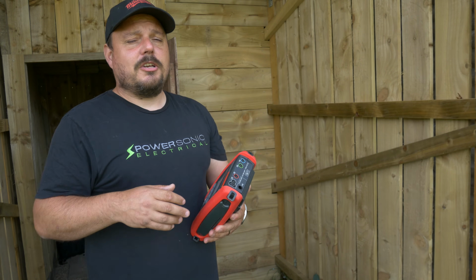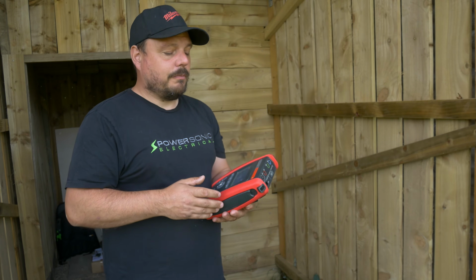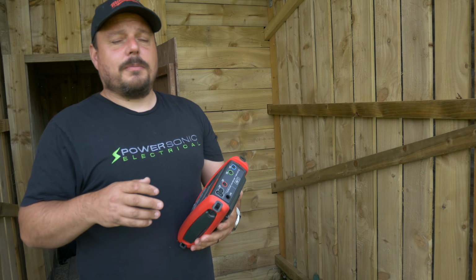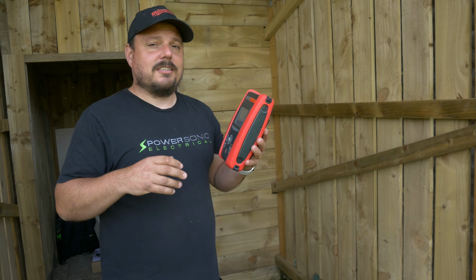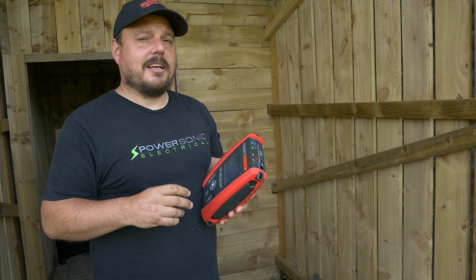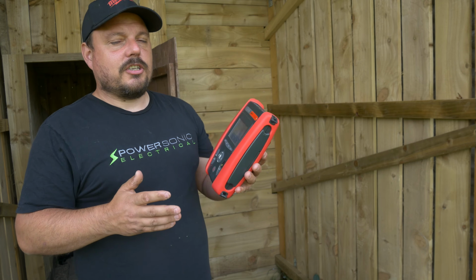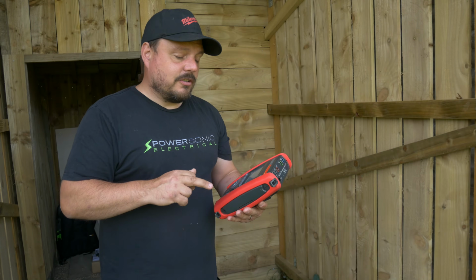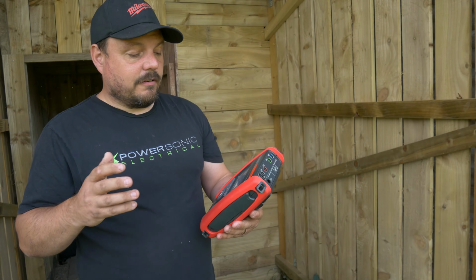It'll do environmental measurements in terms of temperature with the suitable probes. It can do a volt drop measurement as well, so you can use this to determine what volt drop you might have at end of line, and I've demonstrated how you do that on the channel before with this instrument. You can also do your phase sequence measurements if you're on a 3-phase system.